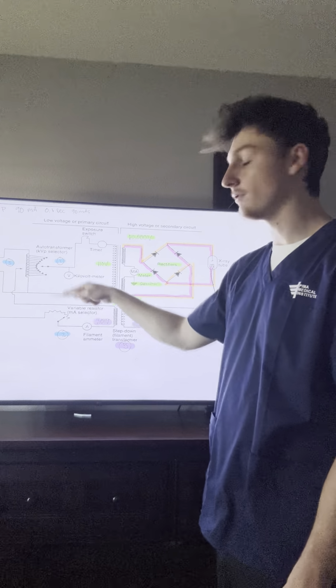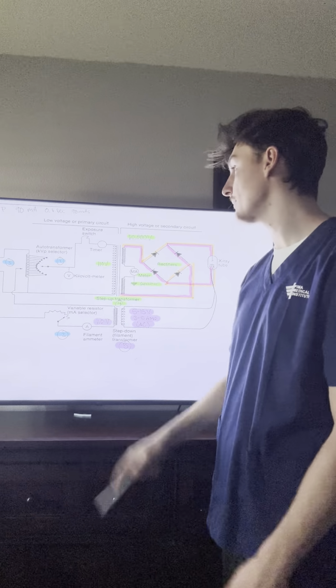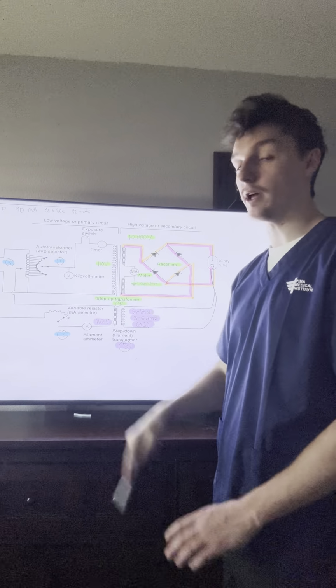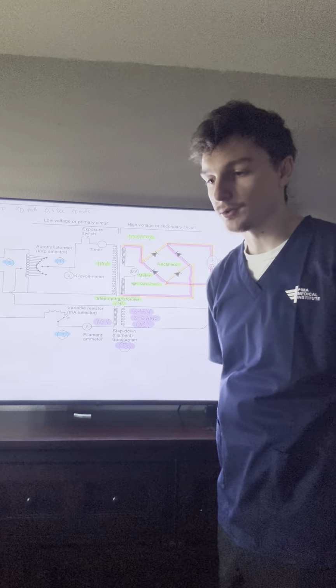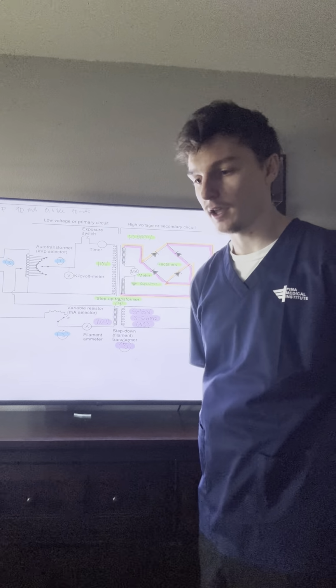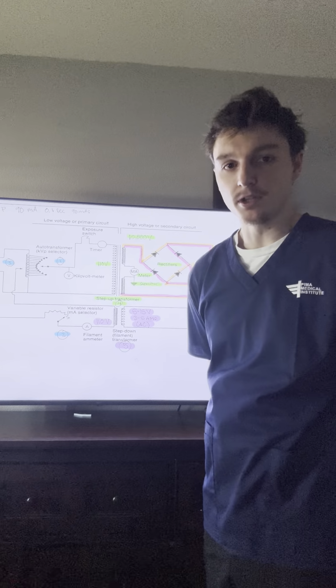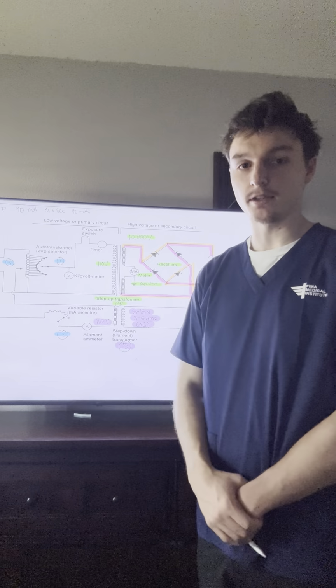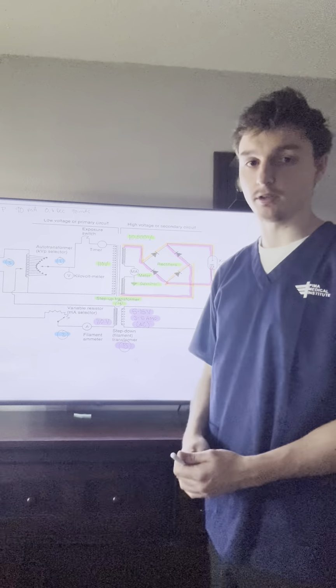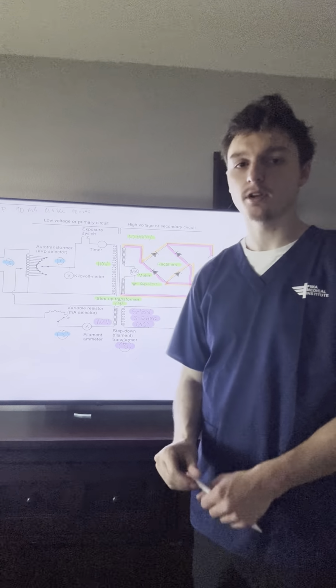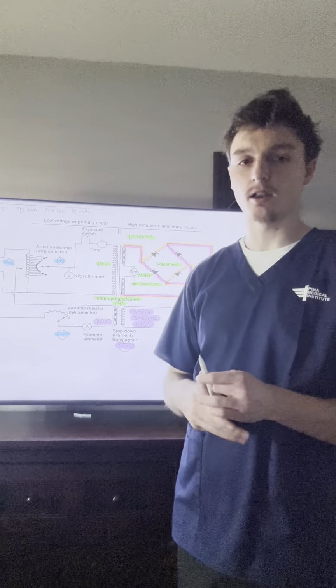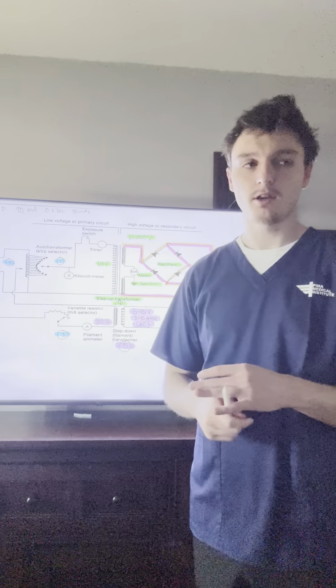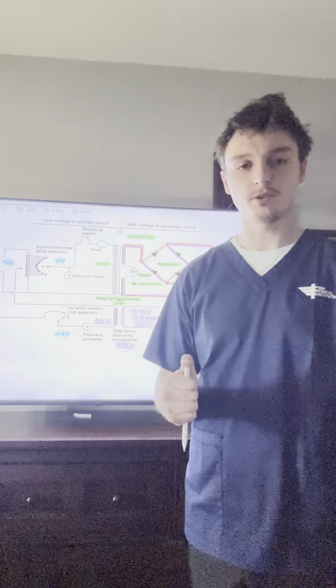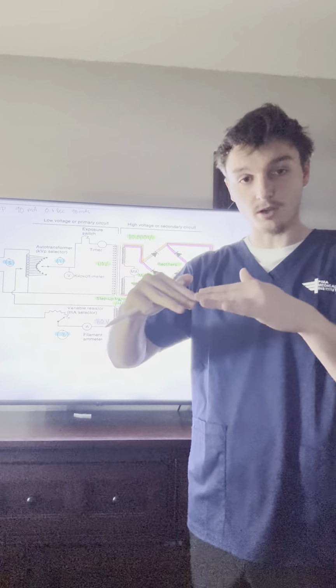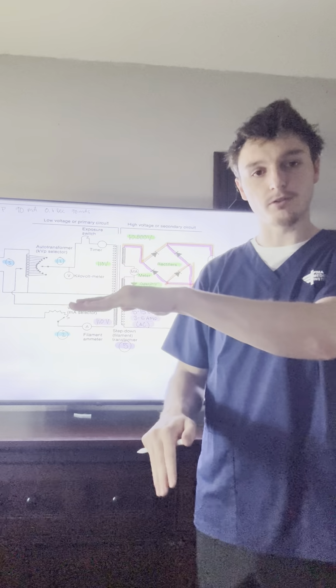Now that we've finished these first 3 points of induction, we can talk about our exposure switch and our timer. Our timer is going to read that 0.1 seconds, and the machine is going to read that for the allotted time that we pick, so it's going to be the 0.1 seconds. You can describe the exposure switch as kind of like a bridge, in the sense that when you're pushing it down, the bridge is going to come down and traffic can flow through.